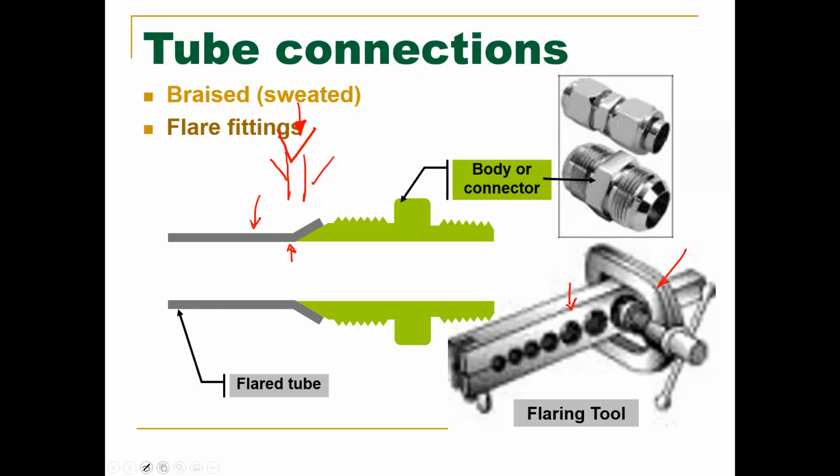All right. These are used, but I don't like them. Not a lot of people like these. They work well for a while, but depending on the material, they will eventually break. And they break a lot faster than other versions. Why is that? Because of what we're doing to the flared pipe. Well, you're warping it, so it loses the integrity that it originally had. So we're warping it. We're expanding the pipe.